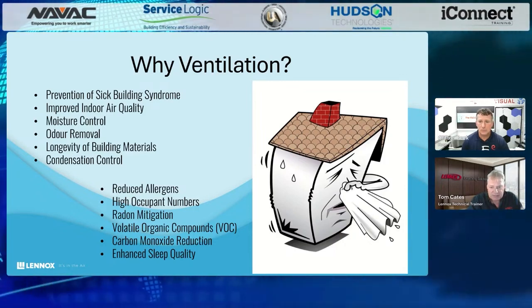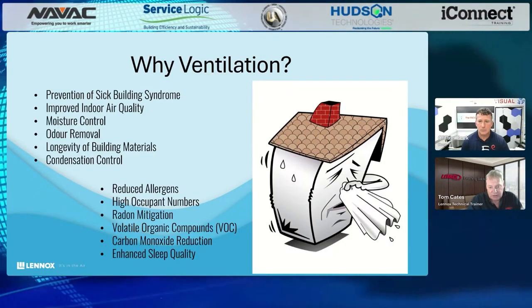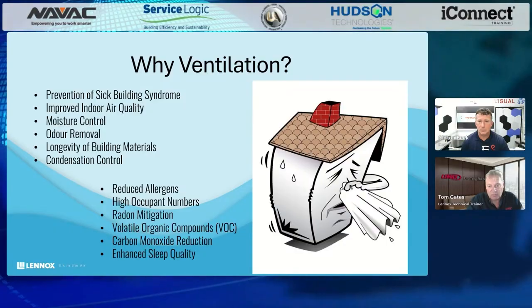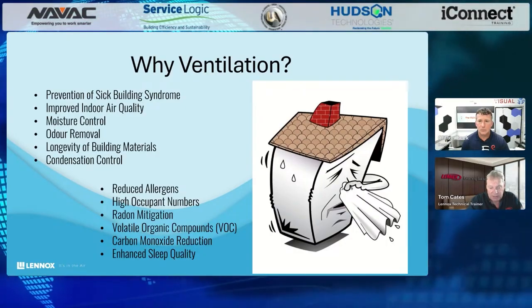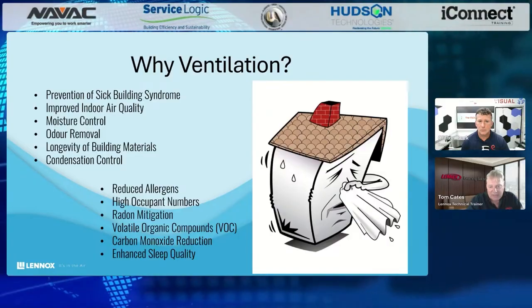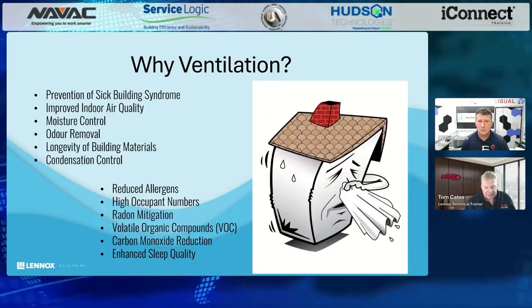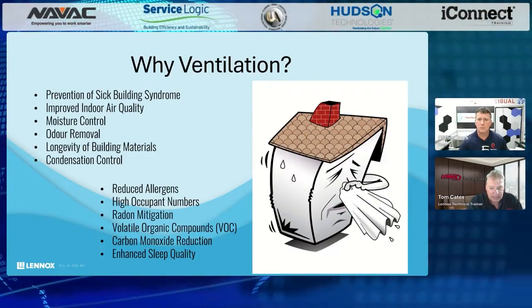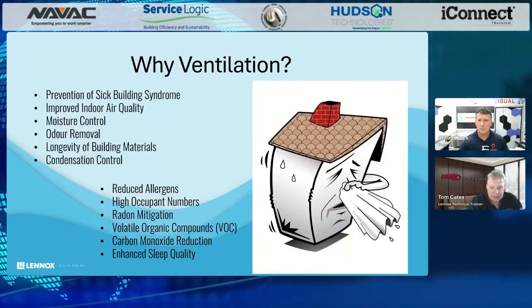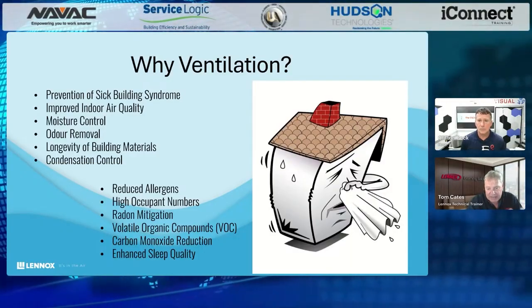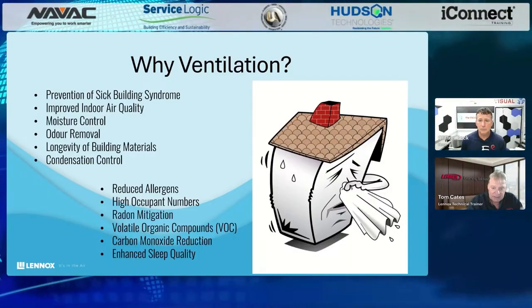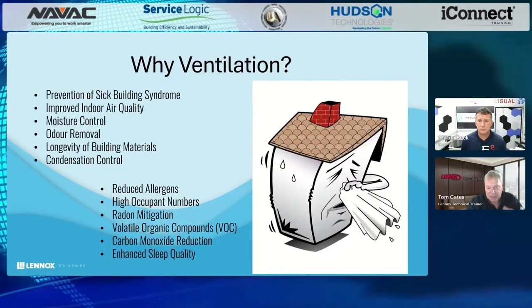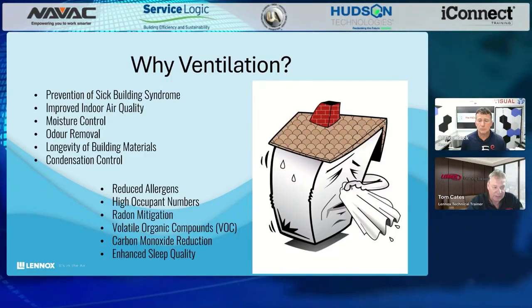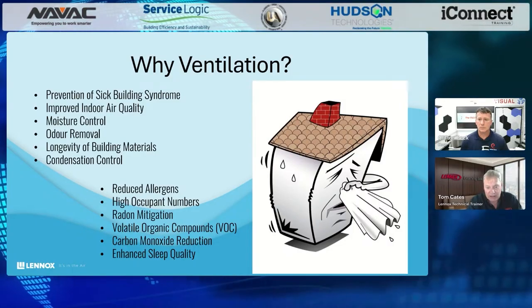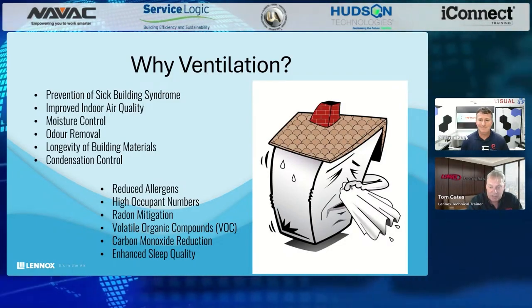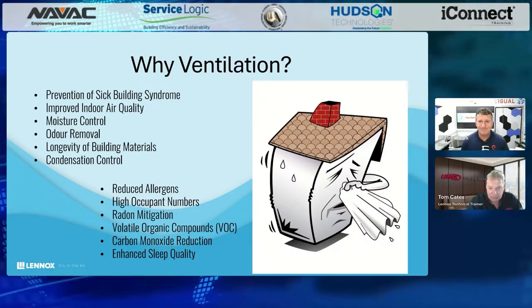Under some circumstances, we can influence moisture, or have some control over moisture influence on the building, through ventilation. It only happens in some very specific scenarios where we can actually influence the relative humidity of a space. For us up here in Canada, it has to do with that relative humidity between temperatures. When temperature changes, so does relative humidity. So when we bring in cold outdoor air in the middle of January and we warm it up, it actually has a drying effect on our building.